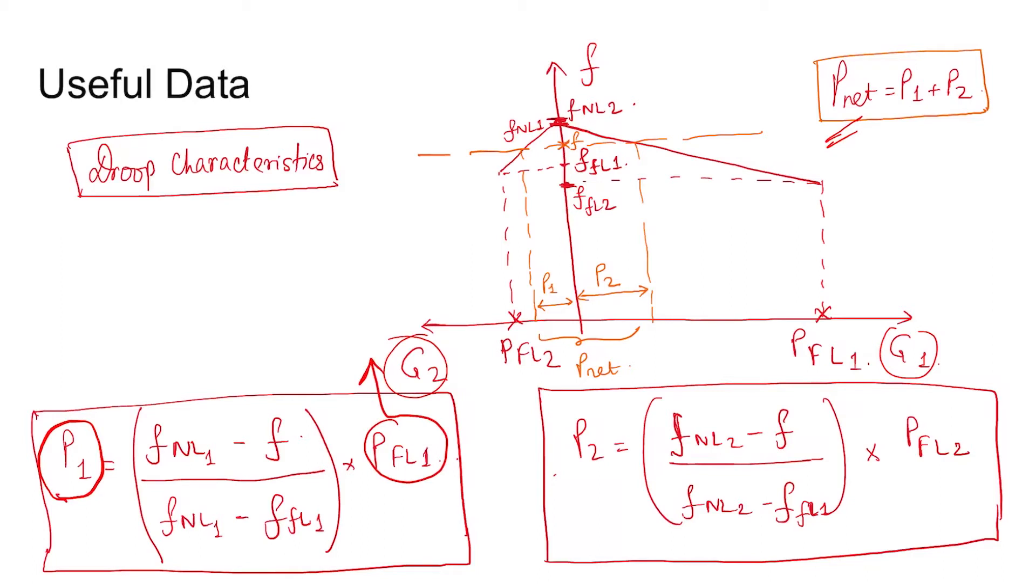As the full load capacity increases, the power sharing capacity also increases. And as droop reduction, that is f_NL1 minus f_FL1, this term becomes smaller, also this term increases, the capacity of generator one. If the capacity is more, it will share more load.